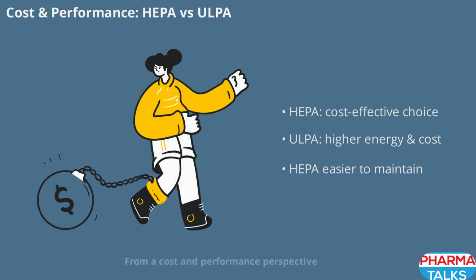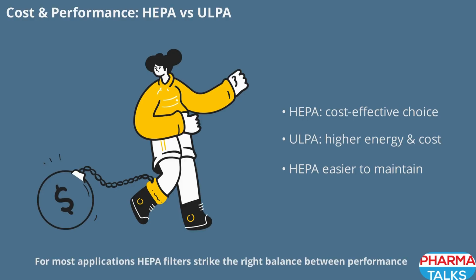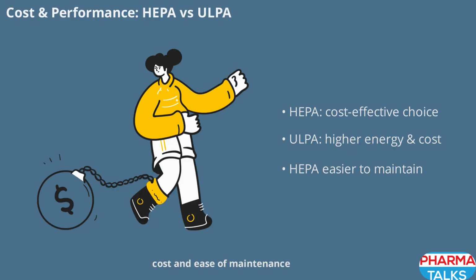From a cost and performance perspective, HEPA filters are generally more practical for pharmaceutical cleanrooms. They are less expensive to install and maintain, and their lower pressure drop means reduced energy consumption. ULPA filters, while offering superior filtration, come with higher installation and operating costs due to their increased resistance to airflow. Additionally, ULPA filters require more robust HVAC system designs to function effectively. For most applications, HEPA filters strike the right balance between performance, cost, and ease of maintenance.